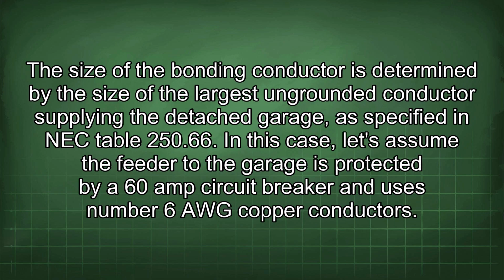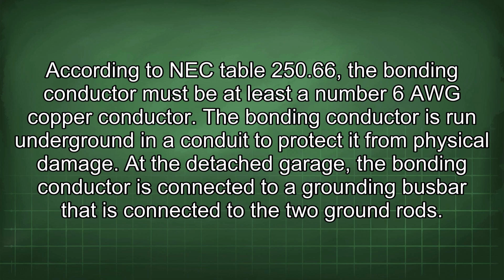The size of the bonding conductor is determined by the size of the largest ungrounded conductor supplying the detached garage, as specified in NEC Table 250.66. In this case, let's assume the feeder to the garage is protected by a 60 amp circuit breaker and uses number 6 AWG copper conductors. According to NEC Table 250.66, the bonding conductor must be at least a number 6 AWG copper conductor. The bonding conductor is run underground in a conduit to protect it from physical damage.